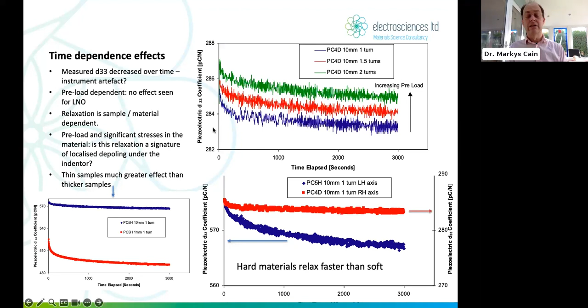But what does this tell us? Okay, good practice here would be to make sure that we understand this, and it means, really, I suppose, you're not able to take the measurements very quickly. You would need to make sure the sample's been in there for the same amount of time each time you do the measurement, and that any relaxation or aging, if that's what it is, has been manifest and is spent.